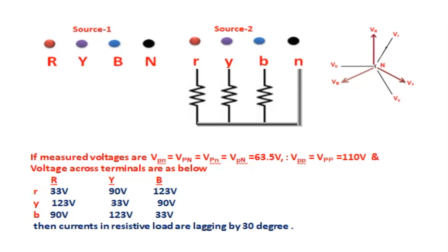In this diagram, source 2 voltages are lagging source 1 by 30 degrees, and the source 2 terminals are connected to a resistive load. The measured voltages — phase-to-neutral of both sources, source 2 neutral to source 1 phase, source 1 neutral to source 2 phase — confirm source 2 voltage = 63.5 V and VPP = 110 V. Terminal voltages across the table are: 33 V, 90 V, 123 V, 123 V, 33 V, 90 V, 90 V, 123 V, 33 V. Currents in resistive loads are therefore lagging by 30 degrees.